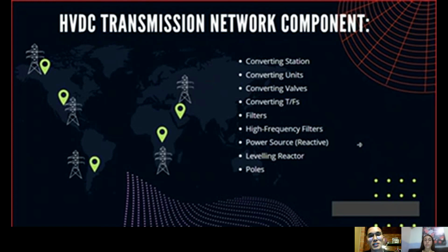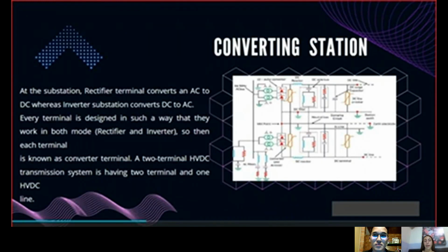HVDC transmission network components. The main components of an HVDC system are mentioned below: converting station, converting units, converting valves, converting transformers, high frequency filters, power source, smoothing reactors and poles. Converting station. At the substation, the rectifier terminal converts AC to DC, whereas the inverter substation converts DC to AC.